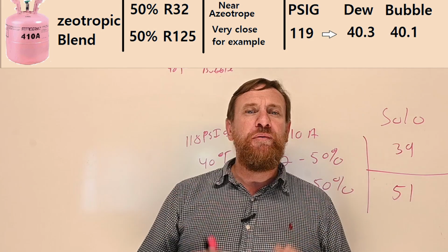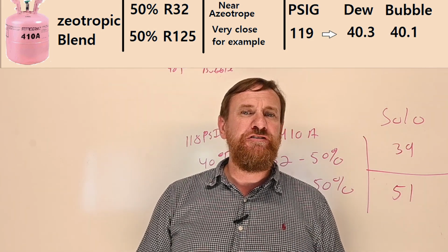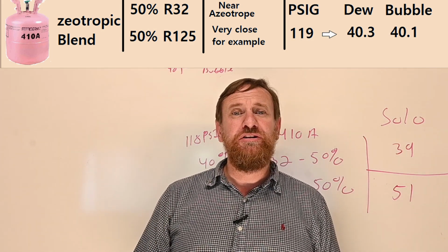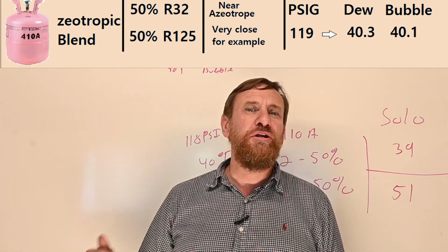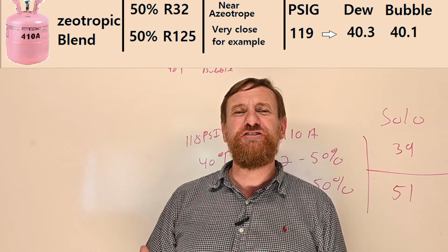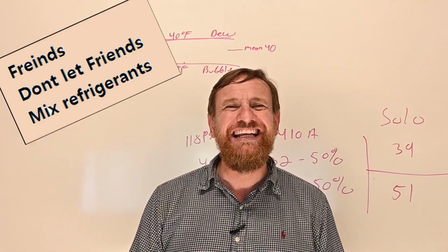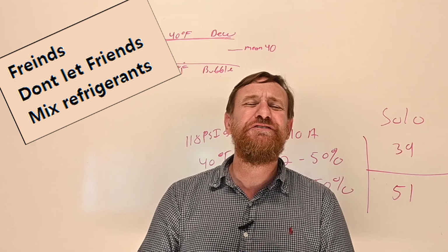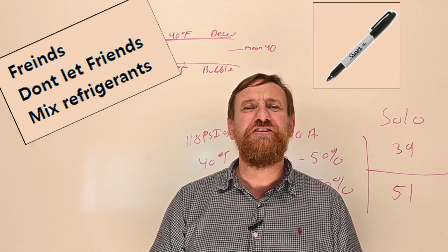Make sure we have the proper refrigerant, the AHRI identified approved refrigerant with a temperature pressure chart that goes with it. Now we know superheat subcooling, or at least we know superheat with dew point, super dew to the rescue, and subcooling with bubble point, 5 degree down bubble. We all live in a red submarine, red for subcooling, high pressure subcooled liquid. And please, please, I beg you, do not mix refrigerants, and if you do, label it mixed on that unit so somebody else knows what's happening.